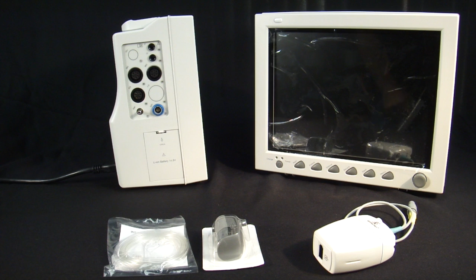You will also notice that all of our monitors ship with open IBP ports, and so the invasive blood pressure parameters are shipping standard. The boards are built into the machine. We used to charge extra to have those ports open. We are now just shipping with those ports open at no charge. The only thing that you would have to buy if you wanted to enable those ports is a pressure transducer interface cable that converts the side of the machine to the disposable kit of your choice. We have BD, Hospira, Edwards, and a couple other options available for you.